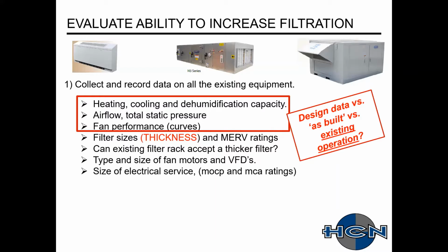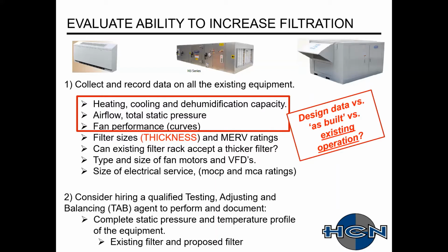All right. So now the standard also suggests you consider hiring an air balancing company or person to perform and document what they're calling a complete static pressure and temperature profile of the equipment. A little bit of weird terminology. And then they're asking you to consider doing that for your existing equipment, and also for your proposed upgraded filter.